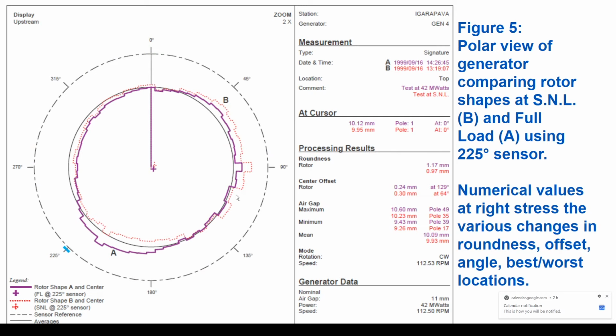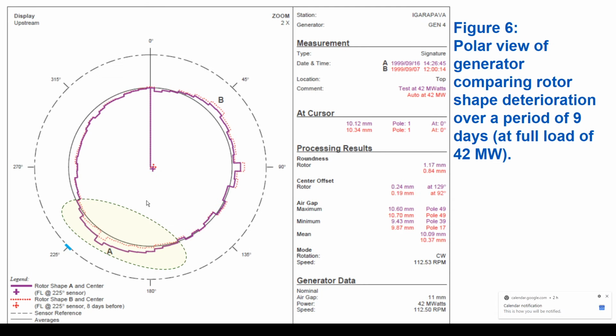If we look at the polar graph, we can see this section here. Okay, this is at speed no load, and this is at 42 megawatts, and you can see how increasing the load was actually pulling this part off. Okay, so the OEM was able to come in and do some percussion tests on the rotor rim bolts and found that the rotor rim bolts on this unit actually broke when they tested them. So they replaced all the rim bolts with better quality bolts on all the units, and they never had a problem afterwards.